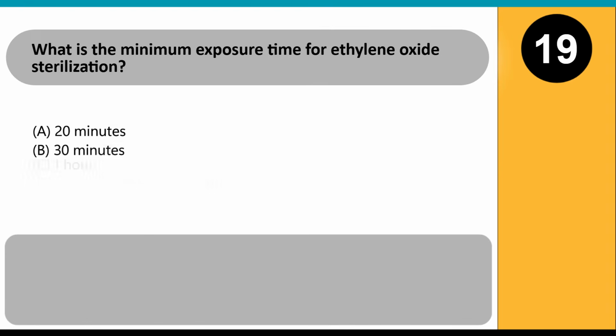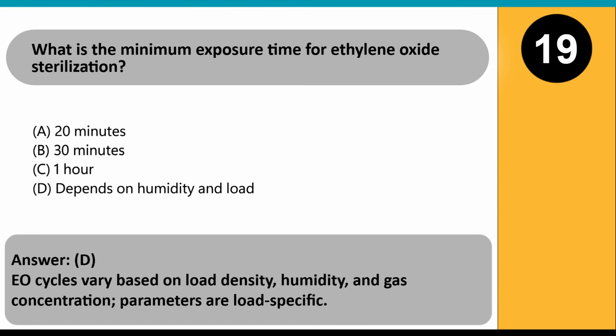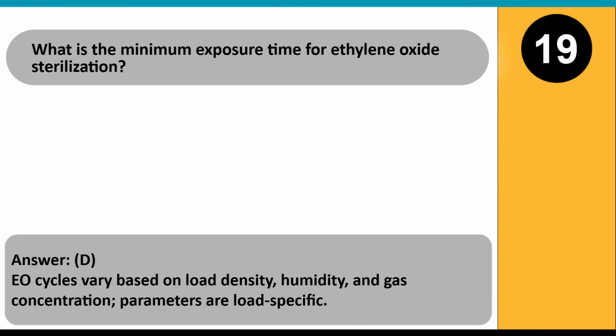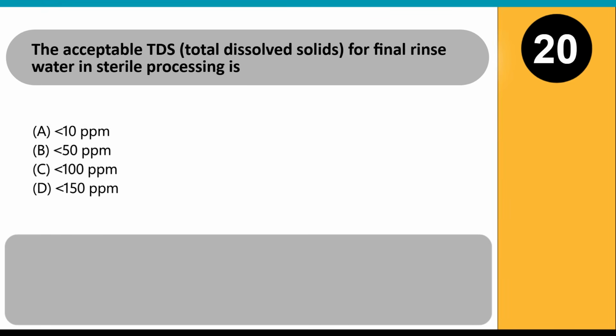What is the minimum exposure time for ethylene oxide sterilization? A. 20 minutes. B. 30 minutes. C. 1 hour. D. Depends on humidity and load. Answer: D. EO cycles vary based on load density, humidity, and gas concentration. Parameters are load-specific.